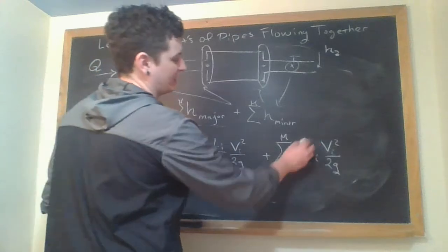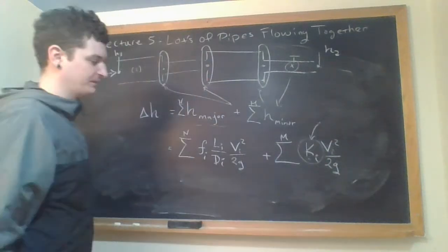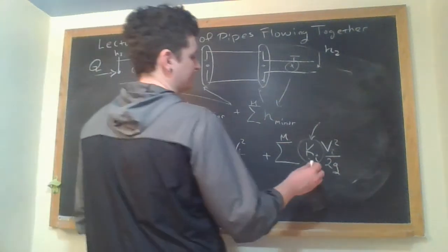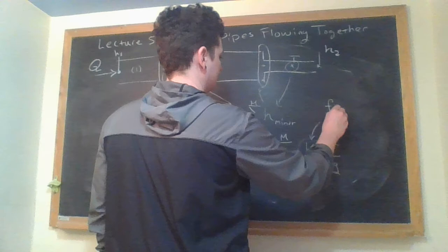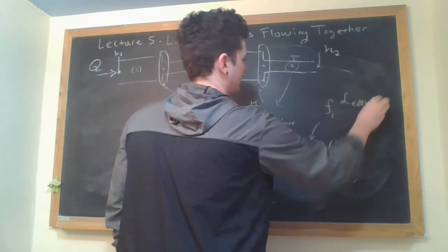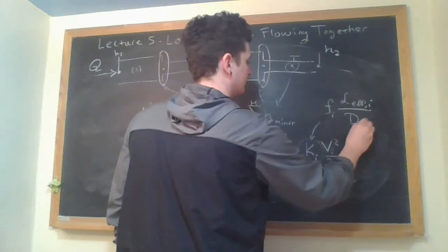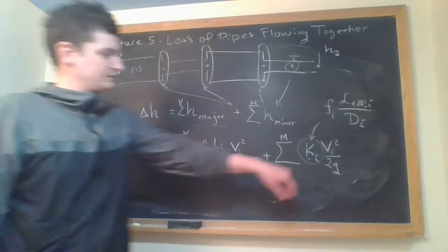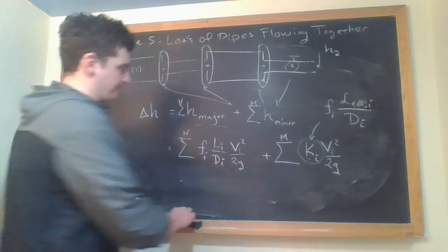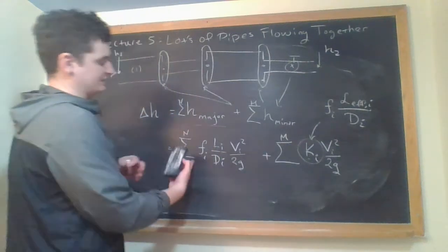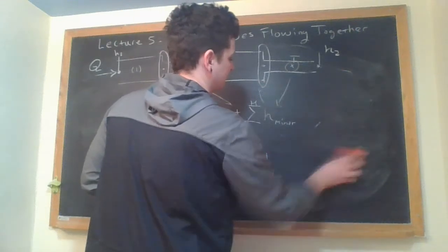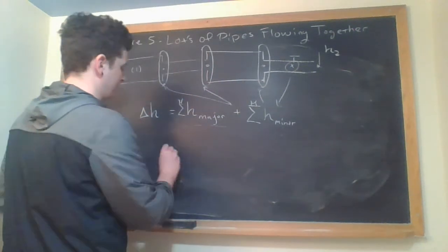Now, this is the reason why you'd want to calculate these effective lengths, if you remember. Because if I calculate the effective lengths, everything would look exactly the same. I could turn this into something like this, with the lengths L_i and diameters d_i. If I calculate effective lengths for these resistance coefficients, then everything looks exactly the same, with the friction coefficients, the lengths, and the diameters, and that chunks down your whole piping system.